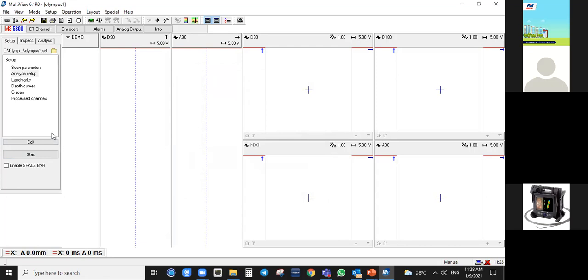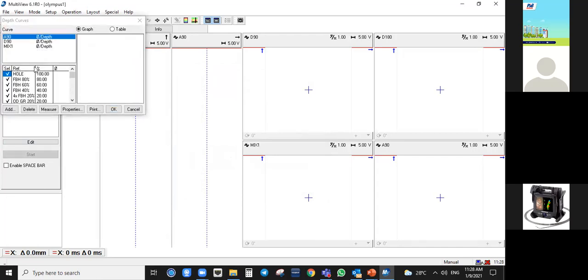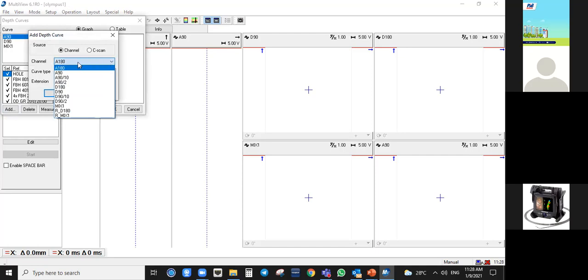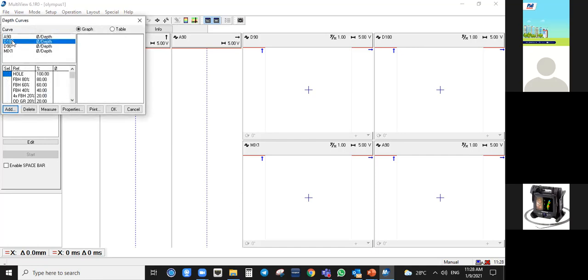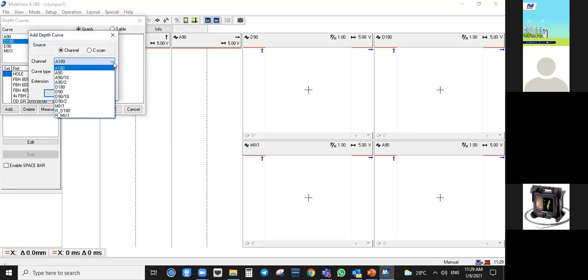Next that you need to do is under depth curves. Under depth curves, what we usually do is add 2 more channels for the depth curves. To add 2 channels, we press add here. We usually choose D180. So you have D180 here, you have D90, and then next that you need to add, because you added 2 OD grooves, 40% and 60%, is another channel, which is A90. But instead of phase over depth, when it comes to curve type, you choose V over depth.